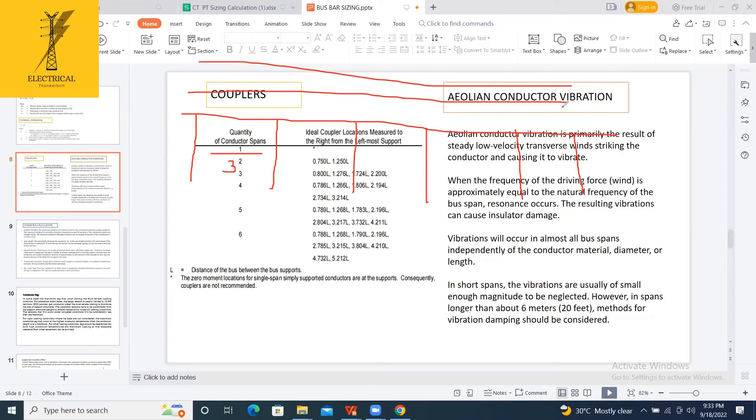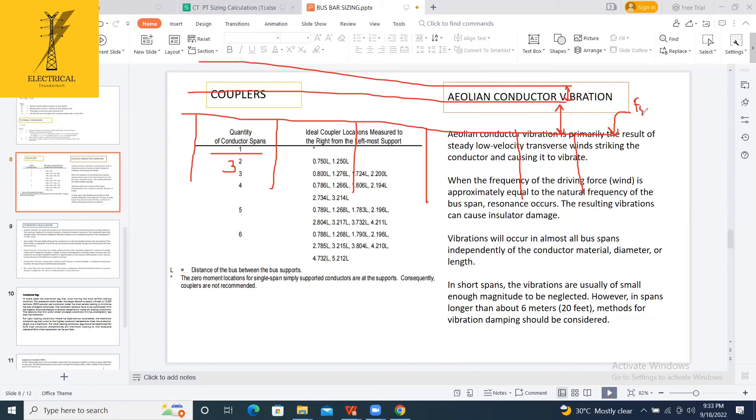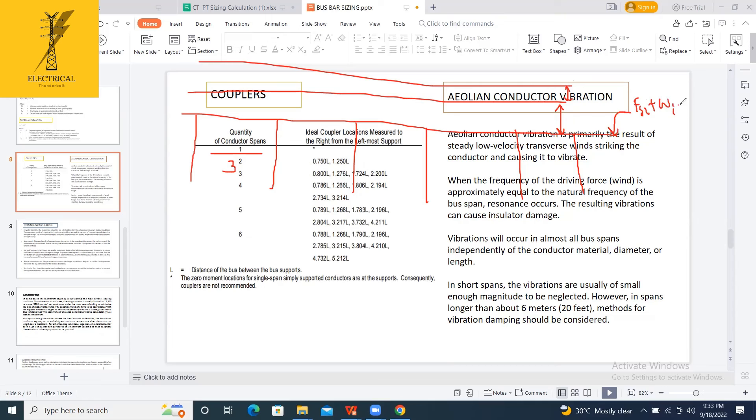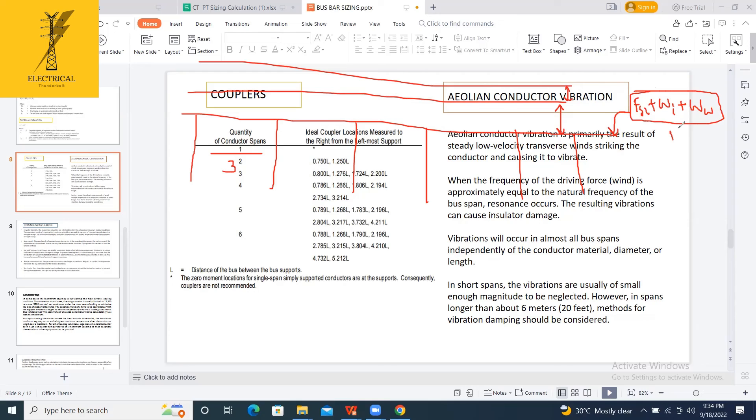What would be the short-circuit forces acting on these conductors, which is one kind of load on this conductor, the short-circuit forces. And also, if my system is in wind, ice loading areas, I have to calculate the ice loadings, and wind loadings also I have to calculate. All these forces, I am finding the equivalent or resultant force which is acting on this one.